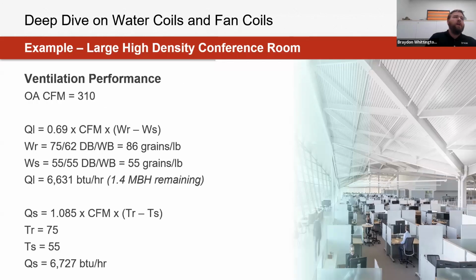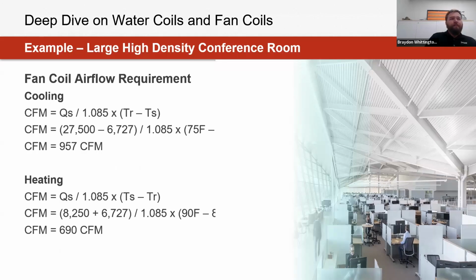But with that, in determining what our required cooling and heating requirements would be, this is going to be based off of then using that sensible load that we've calculated, both from ventilation as well as from some of the other things within that space, to determine what our required cooling and heating airflows are going to be from this product to achieve those targets there too. And I'm noticing now here too, but this is slightly cut off in terms of the entering conditions there too, but this being around that 80-85 mark for our heating side, and then also from our cooling side, that 55 entering for that system there as well.